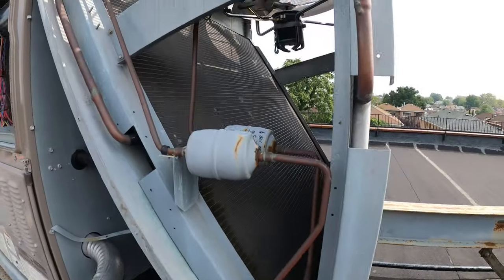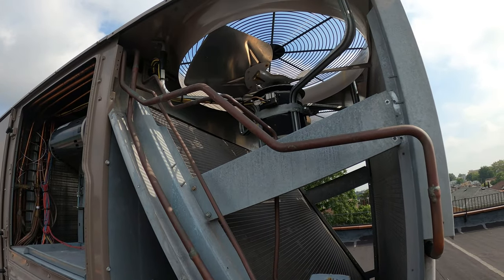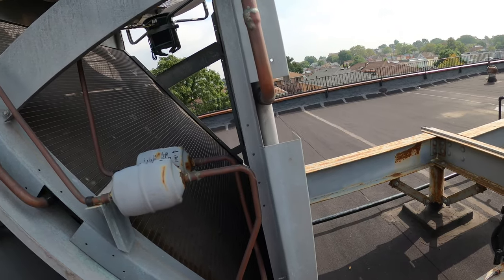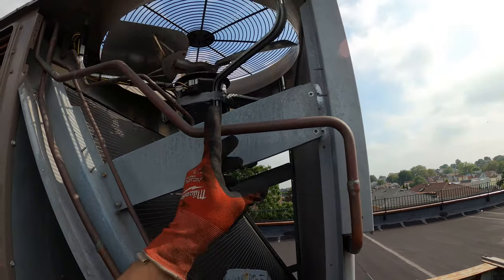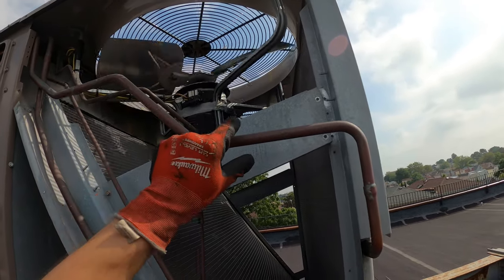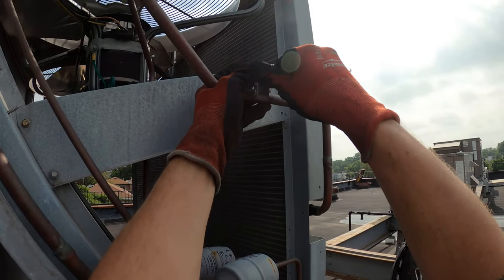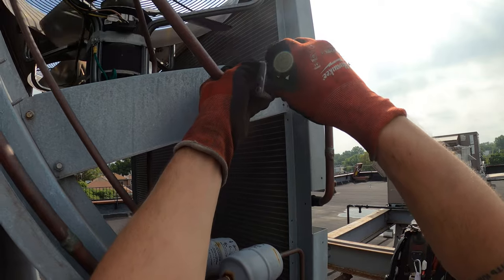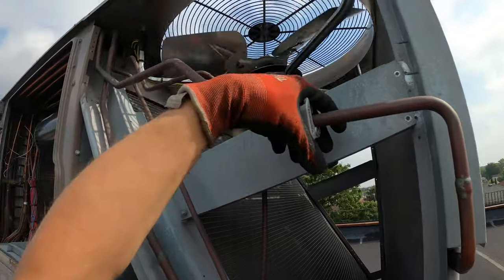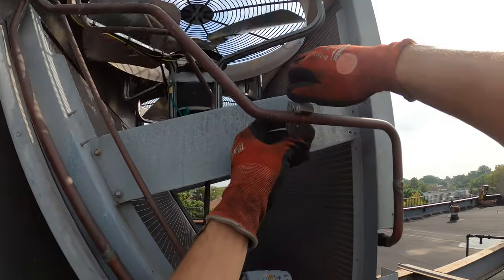Before I remove any more screws — this line is already disconnected. Following the next line, we've got to cut this pipe in a place away from all the other joints so we can easily braze it. Either right here or right here looks good to me. Let's cut this out of the way so that when we drop all the screws, the coil doesn't accidentally drop. Now we just break all the piping here, so let's cut this out and continue.